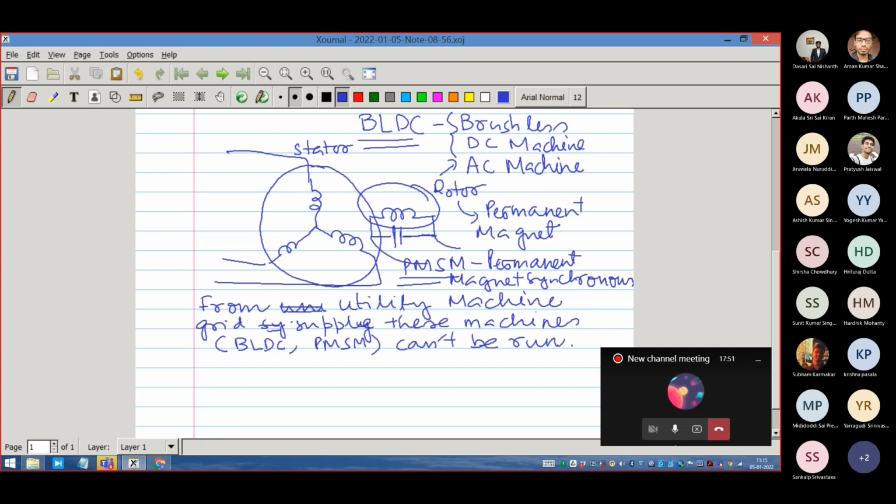But the available source supply, which is mostly available from the grid in the form of either 220-volt single phase or 3-phase, at 50 Hz. The frequency is frozen. So 220-volt 50 Hz or 415-volt 50 Hz, 3-phase. Okay. So those things have now to be suitably modified in order to cater to the requirement of the machine and its more versatile operation.